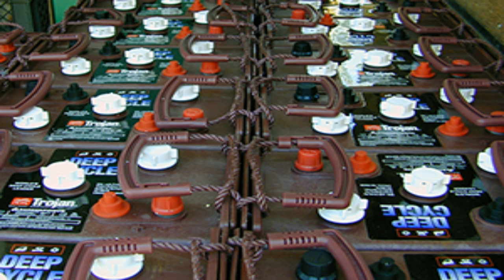Number 5: Keep Your Batteries At An Ideal Temperature. Because temperature extremes cause batteries to deteriorate much faster, it is important that you keep your batteries in a place where the temperature is relatively stable. Aside from enclosed above-ground structures, you can also create a structure that is partially underground — this way the temperature will remain the same no matter what the weather is like outside. Also make sure that the charge controller or inverter system has a built-in temperature compensation feature, because the charge voltage limit of a battery increases as temperature drops and decreases as temperature increases.